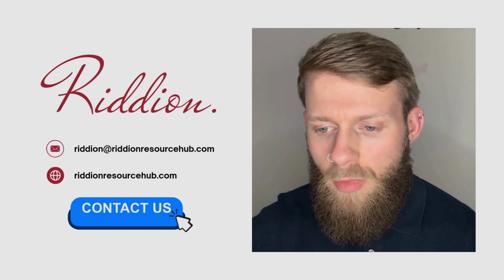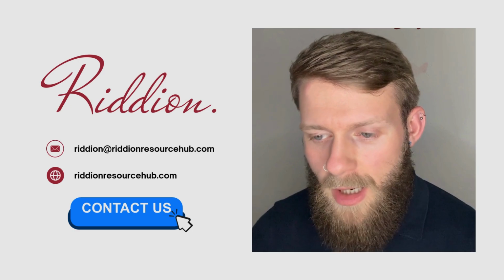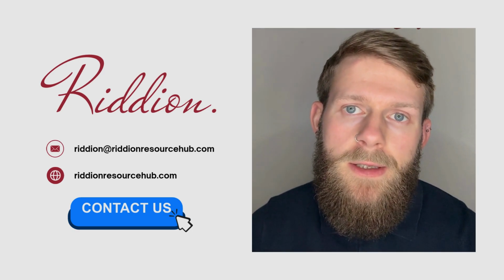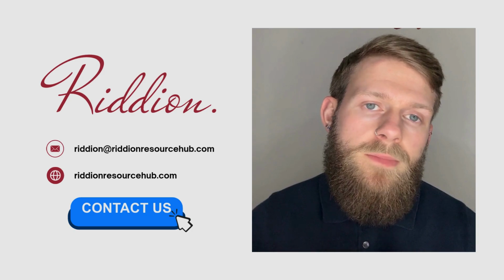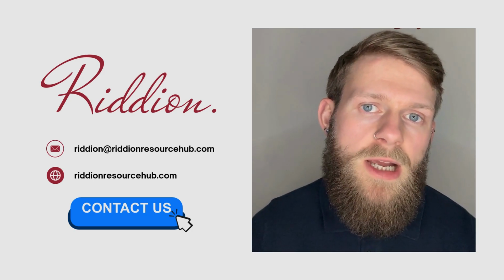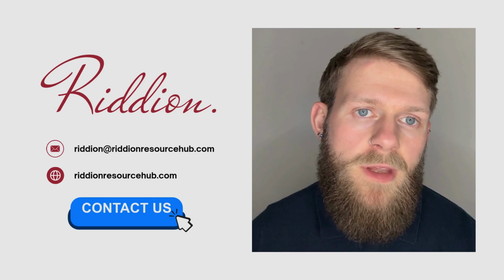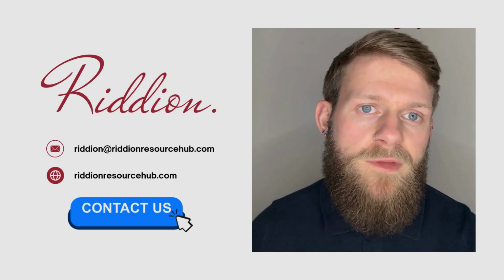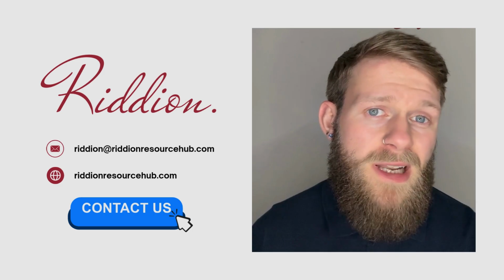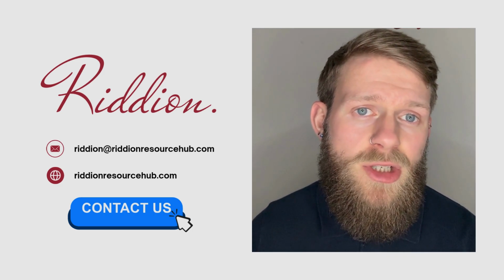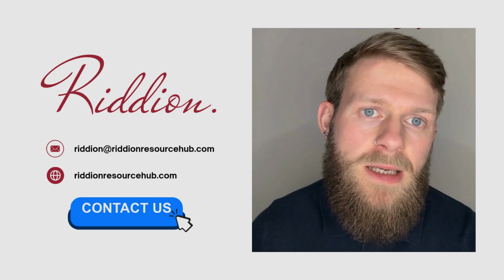So start with question 1. What happens if my UDI is incorrect? So it depends, and it depends on when you catch it. If the error is found before submission, you can fix it internally, run validation checks and make sure your data aligns with what regulators expect.